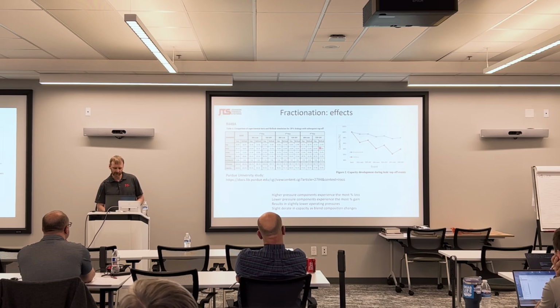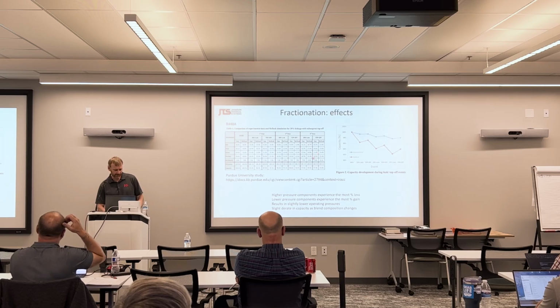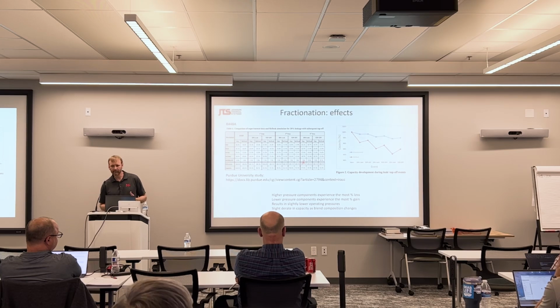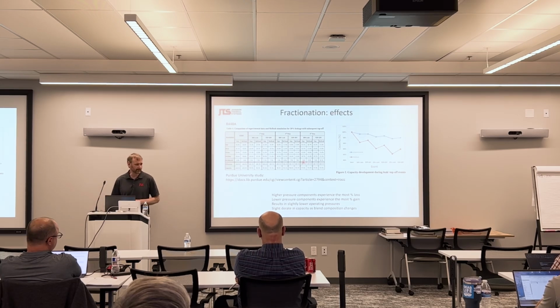If we look at our middle components, they're roughly unchanged. They're pretty close to the same. There wasn't a large amount of leakage on those. And if we look at our lowest pressure component, the R1234ZEE, it actually gained about 2%. I don't know if it actually gained it or if it's just an observed gain. Well, it would be gaining it as you add more refrigerant. You're actually changing the composition, so it gained a certain percentage of the lower component refrigerant.